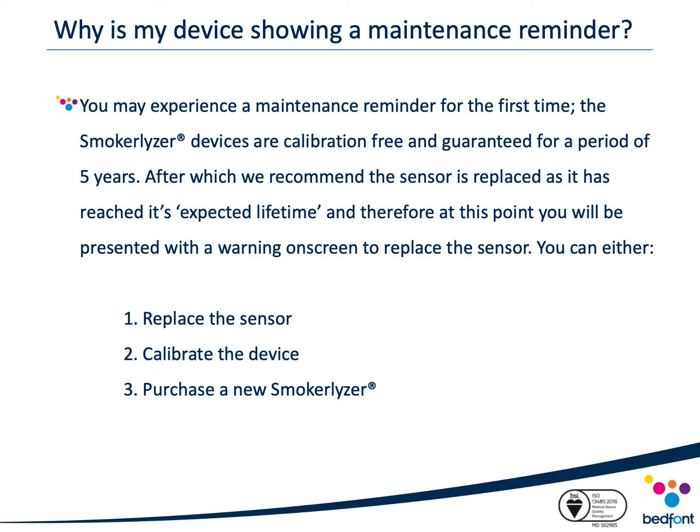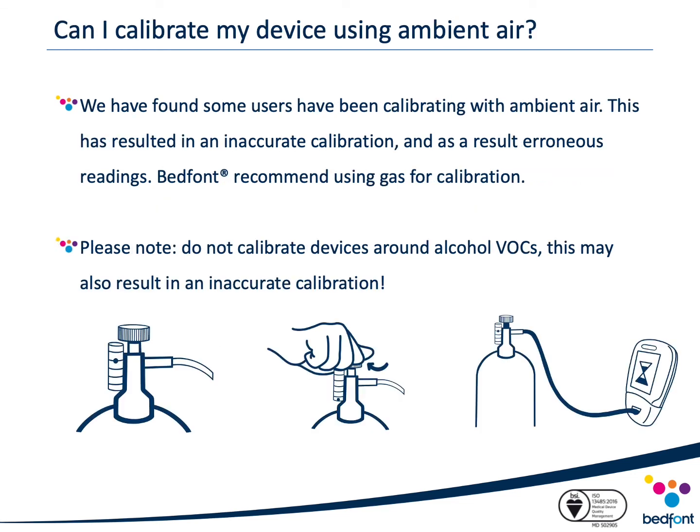You may experience a maintenance reminder for the first time. Smokerlyzer devices are calibration-free and guaranteed for five years, after which we recommend the sensor is replaced as it has reached its expected lifetime. If you experience this issue, you can either replace the sensor, calibrate the device as instructed, or — if the device is outside its guarantee period — it may be more cost-effective to purchase a brand new device, which will be calibration-free and guaranteed for five years. Bedfont have also had reports of devices reading incorrectly due to users calibrating with ambient air, resulting in inaccurate calibration and erroneous readings. Bedfont therefore recommend using gas for accurate calibration. It is also important not to calibrate devices around alcohol VOCs, as this can result in an inaccurate calibration.